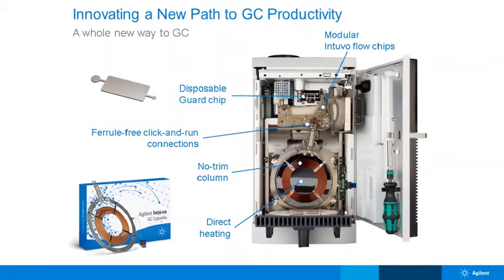And what we have here is instead of an air bath oven, it's direct heating, it's a hot plate. And we have specific columns that fit the column against that hot plate. So it's an ever increasing radius, but only one column thick. Now the benefit of this is you can heat at 250 degrees C per minute throughout the whole temperature range.